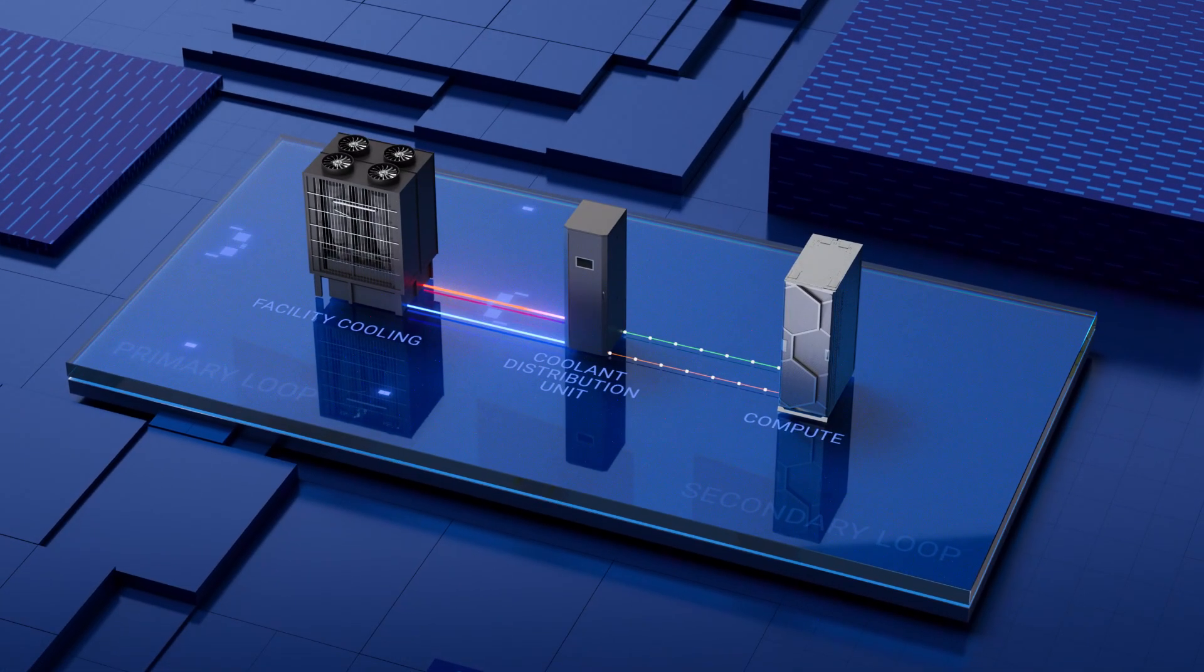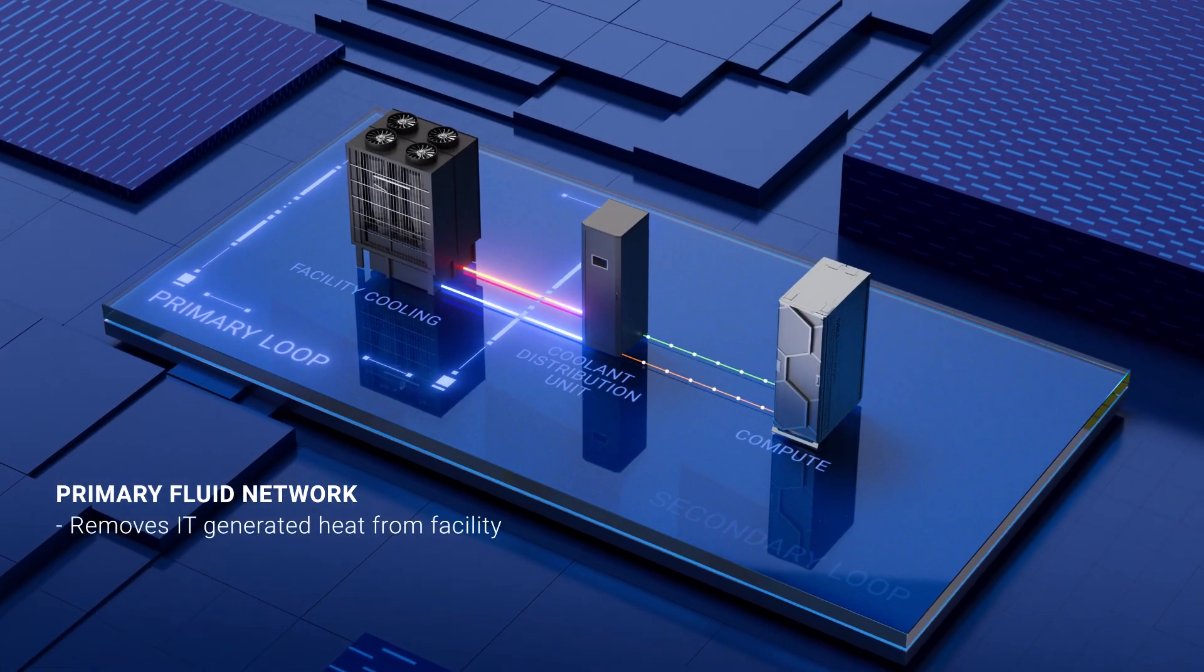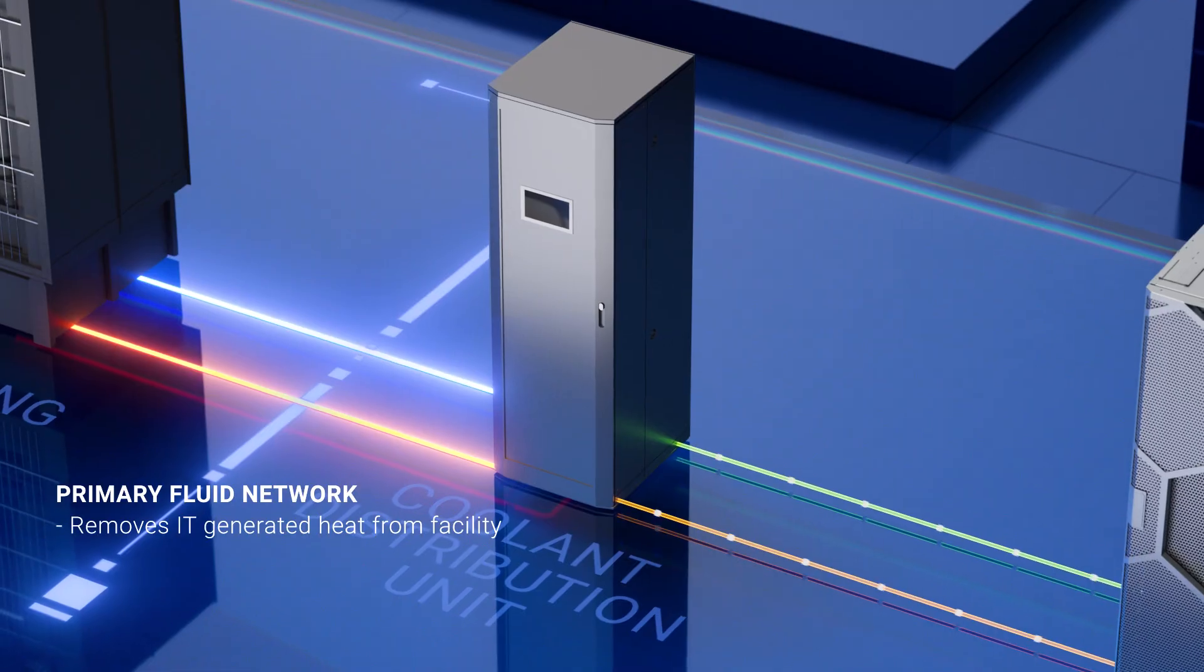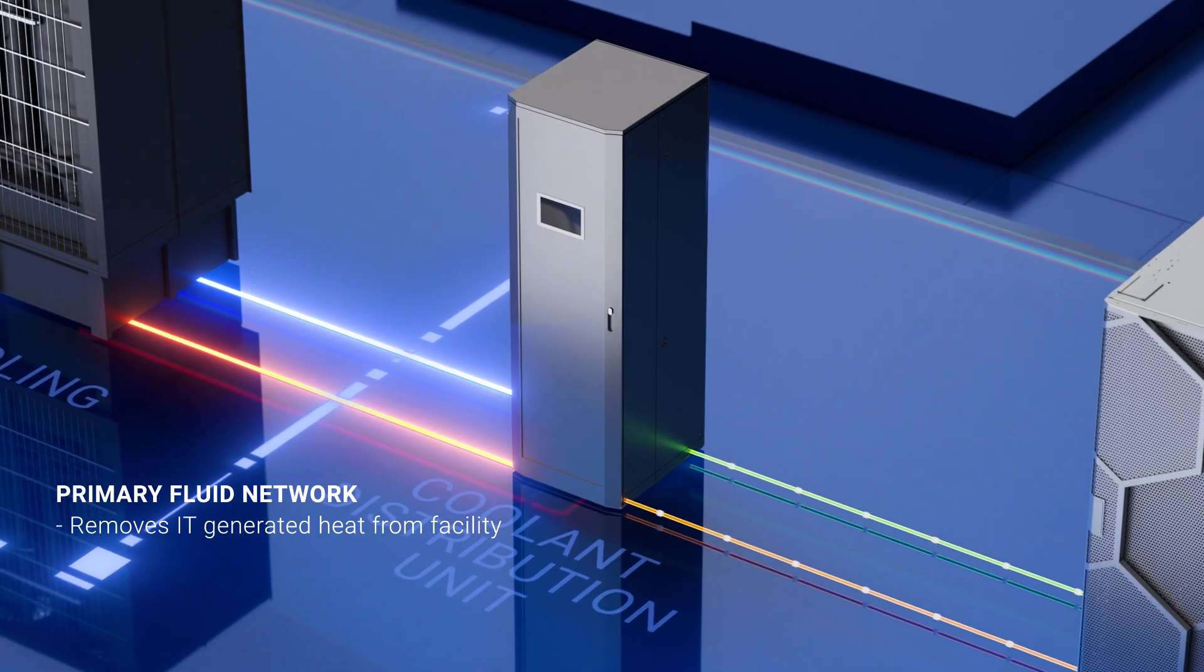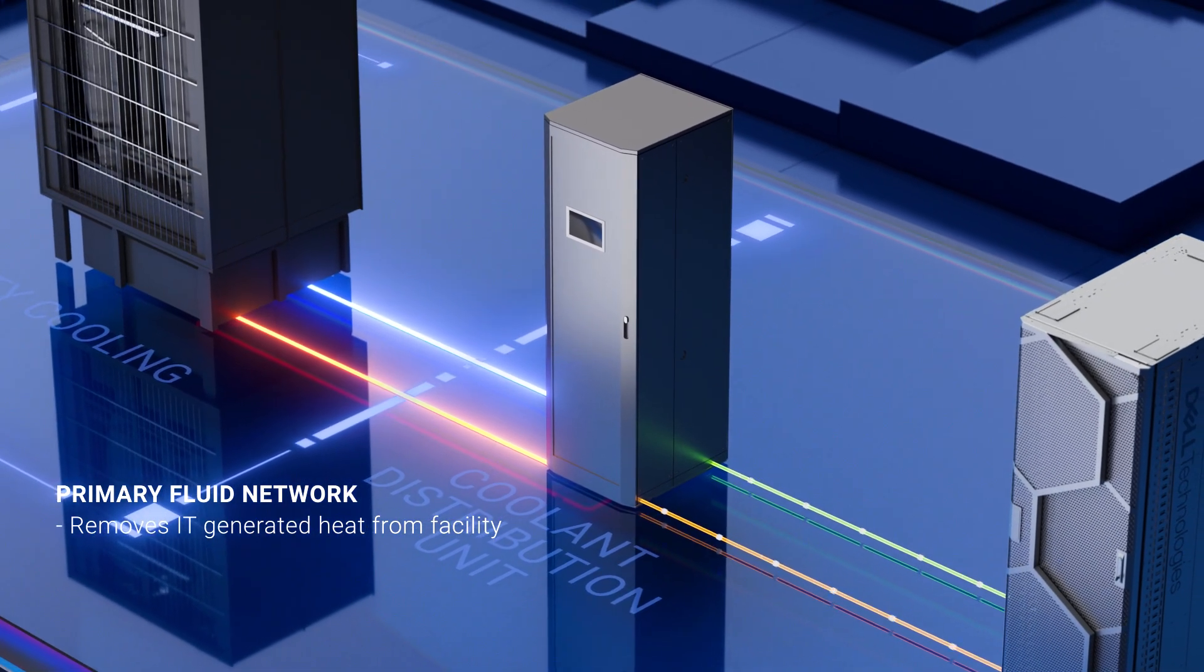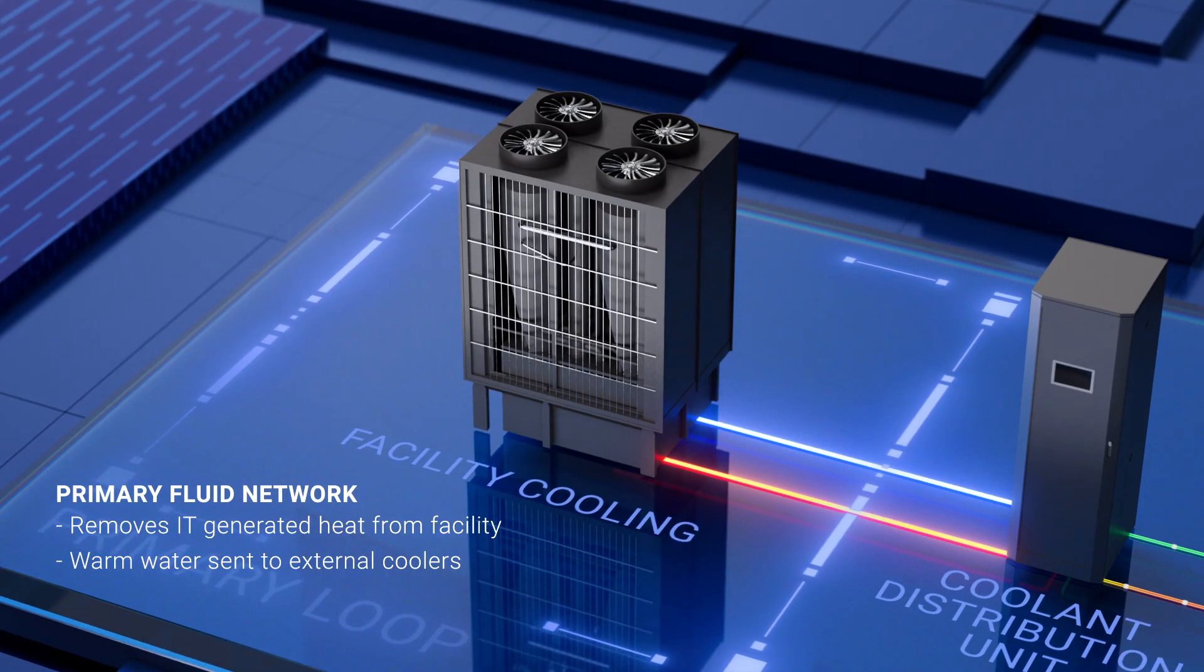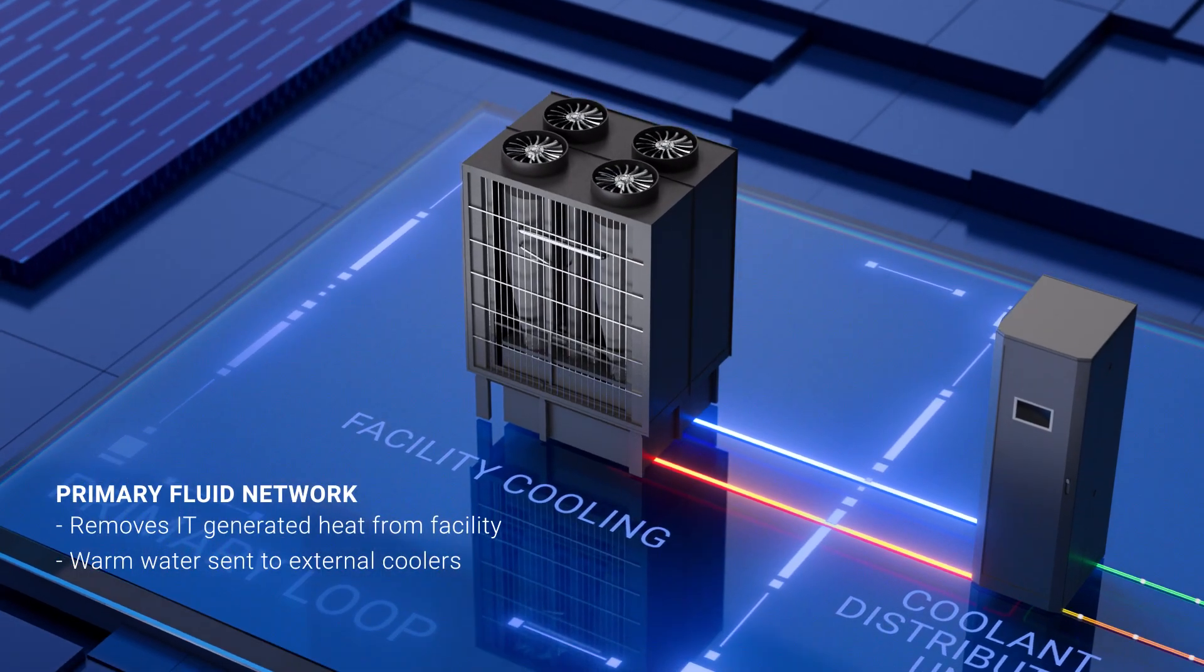The Primary Fluid Network or Facility Water System, FWS, removes IT-generated heat from the facility. Cool supply water enters the CDU and the CDU returns warm water after exchanging heat with the secondary fluid network. The warm water is then sent to external cooling systems, including chillers or cooling towers, cooled and recirculated.